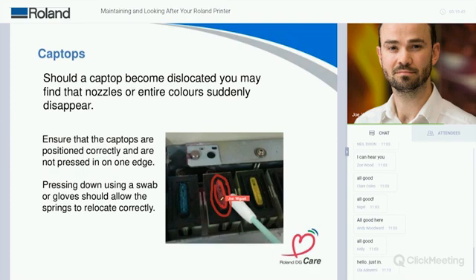Now, this is one of the common problems that I see out on site. Basically, what can happen is if, for example, you accidentally nudge the cap top out of position when you're doing your manual cleans, it can cause the cap top to stay stuck out of position. So what can happen then is, instead of drawing ink through the print head, it's not going to form a very tight seal. In fact, it's probably not going to seal at all.